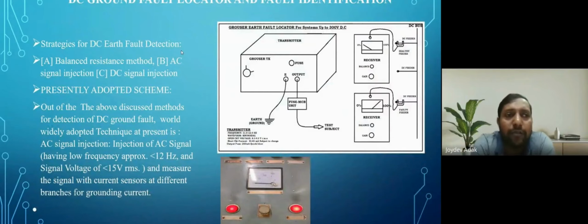For checking DC grounding, there are normally three types of methods. First is the balance resistance method. Here resistance is provided along with two indicators, one between positive and ground and another between negative and ground. If one side gets grounded, the indicator's glow will change; based on the grounding condition, the indicator changes its glow. This is the balance resistance method. The second is the AC signal injection method, and another one is the DC signal method.